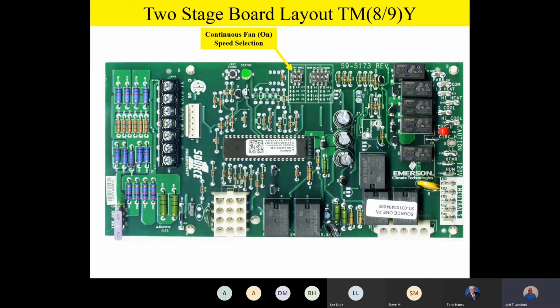So remember, team, again, this is if the homeowner goes to the thermostat sub-base assembly and they switch the fan from auto to on because they want to have continuous fan. How fast does the fan run? Well, that's with those dip switches right there. You can field select your continuous fan speed if there's a G only call from the thermostat on the board.